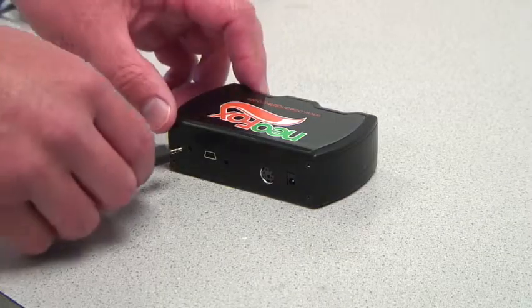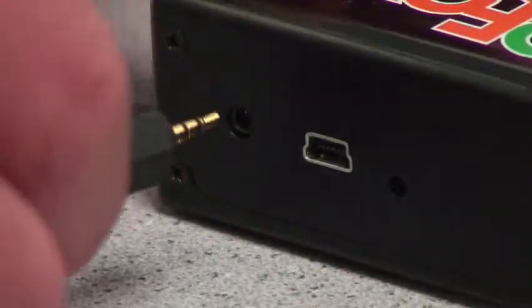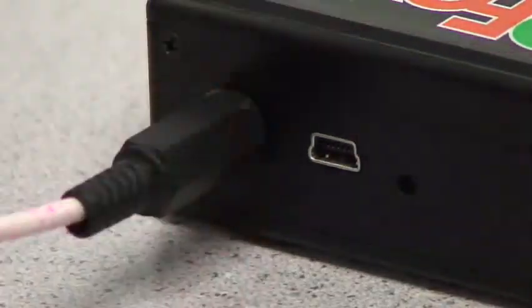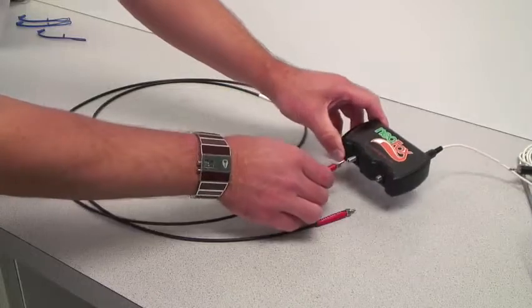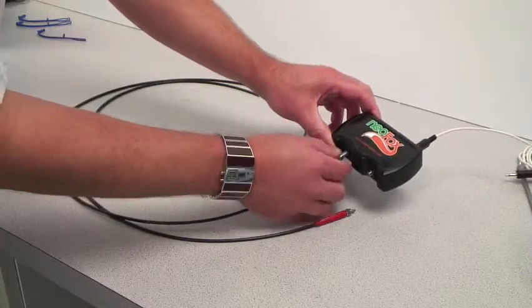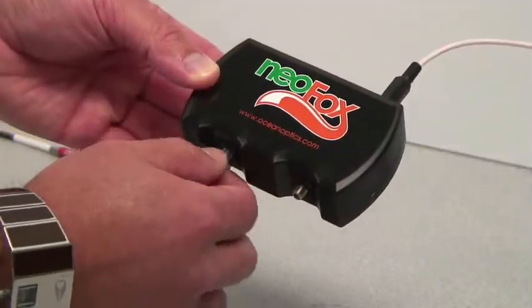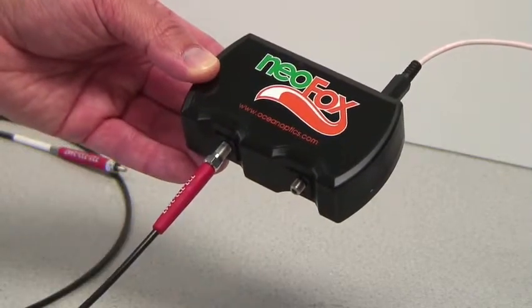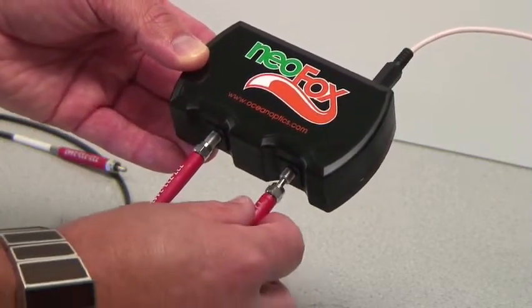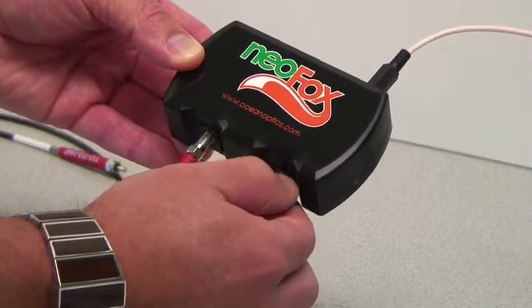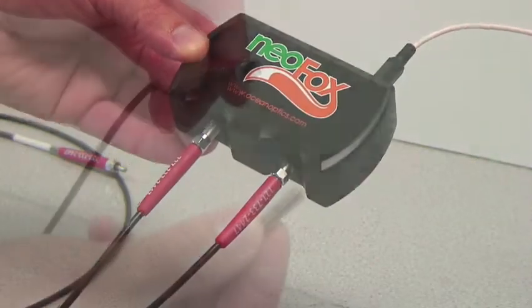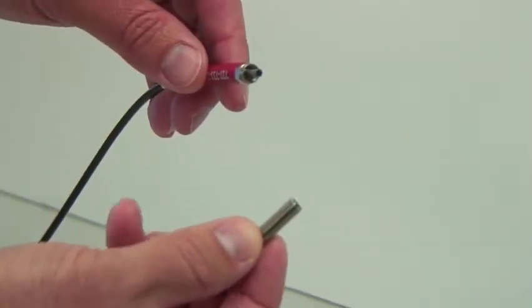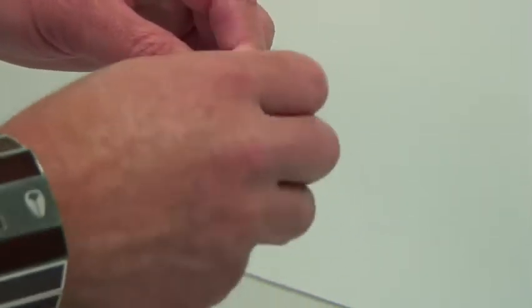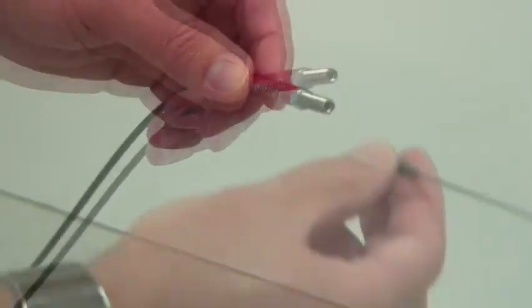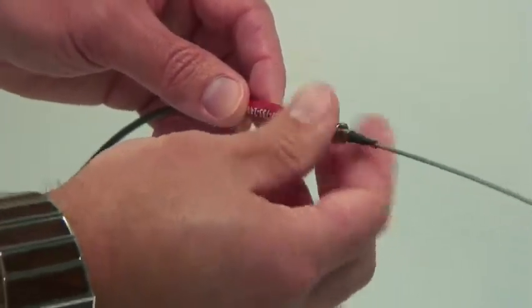If you are using a temperature probe, connect it to the port on the back panel of the NeoFox. Connect one leg of the fiber optic probe to the connector on the LED port on the front of your NeoFox. Connect the other leg of the fiber to the connector on the front panel of your NeoFox. Next, connect the splice bushing provided in your shipment to the free end of the fiber optic probe. Then connect your FOX-ER probe to the other end of the splice bushing.